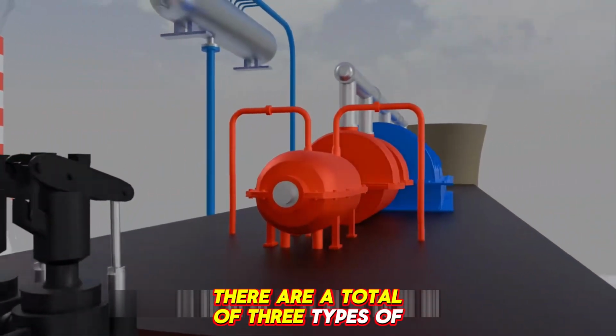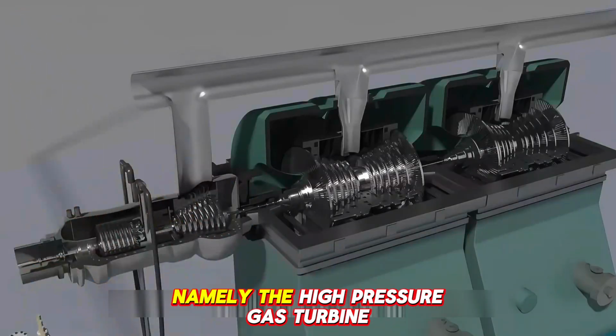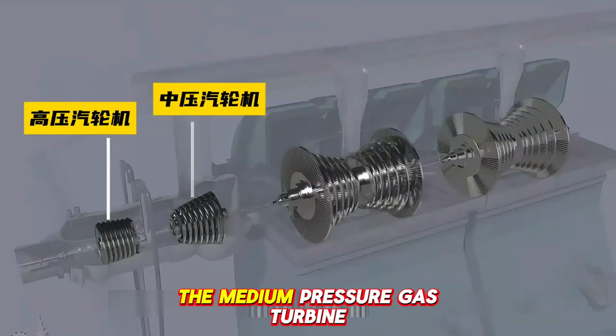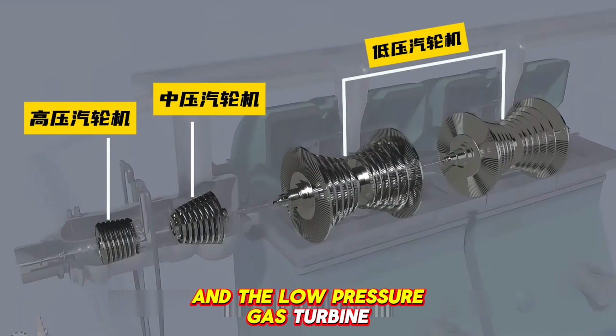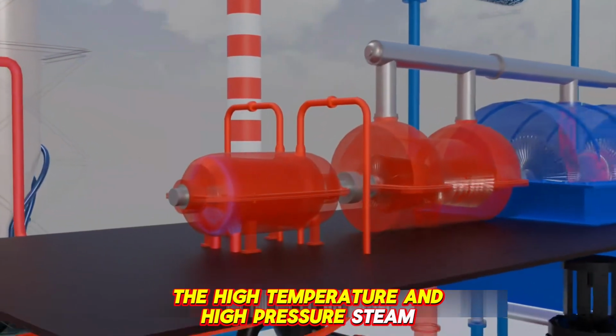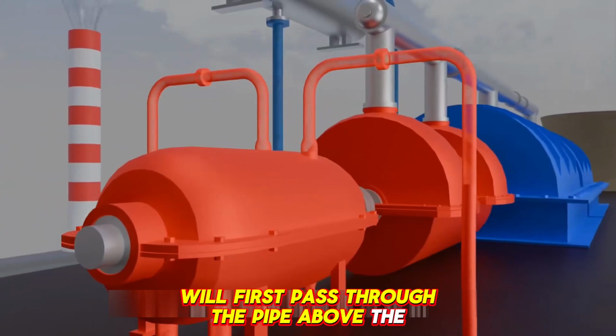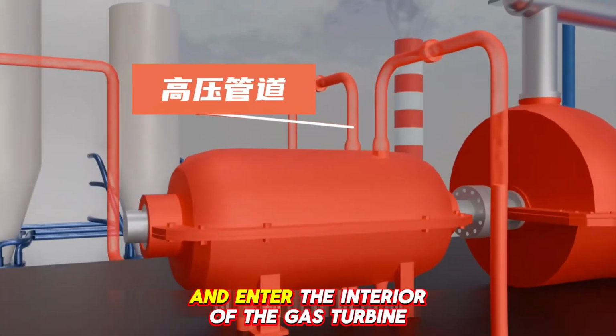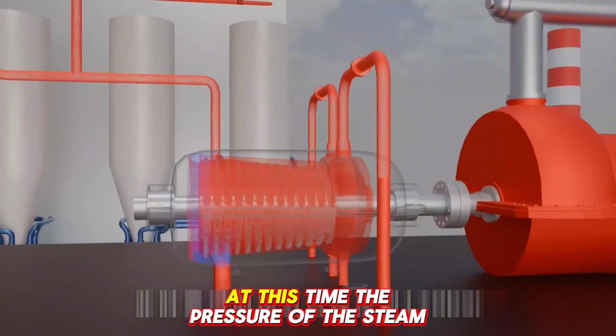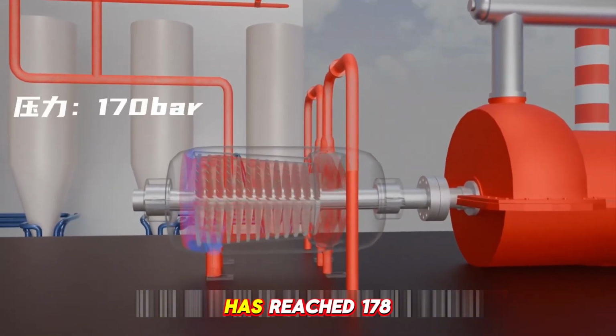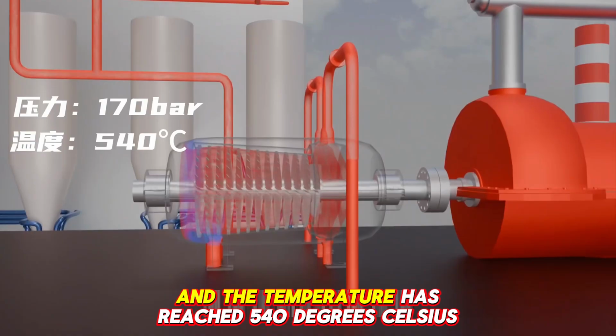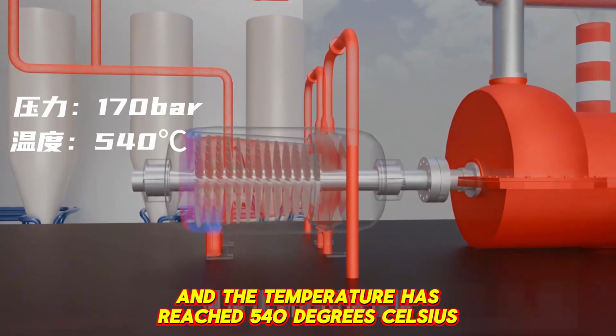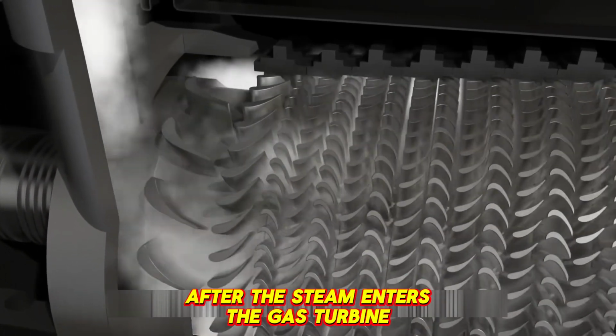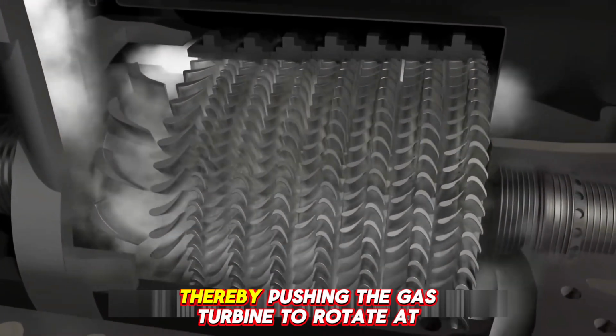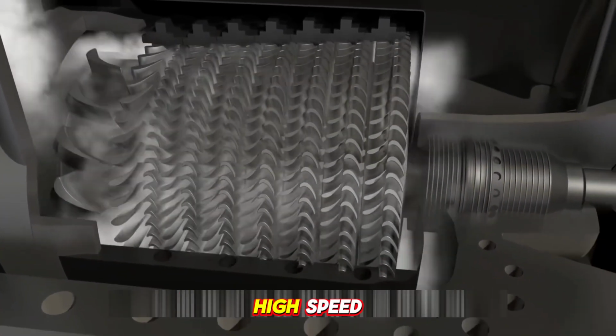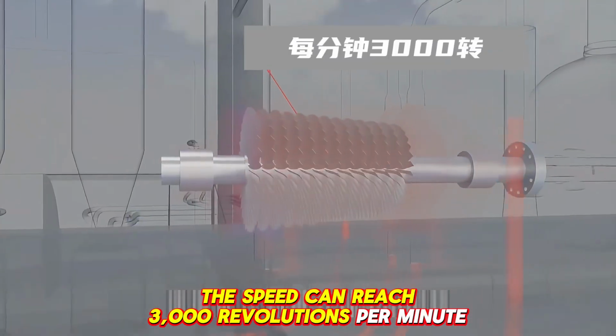There are a total of 3 types of gas turbine units, namely the high-pressure gas turbine, the medium-pressure gas turbine, and the low-pressure gas turbine. The high-temperature and high-pressure steam will first pass through the pipe above the high-pressure gas turbine and enter the interior of the gas turbine. At this time, the pressure of the steam has reached 178, and the temperature has reached 540 degrees Celsius. After the steam enters the gas turbine, it will expand rapidly, thereby pushing the gas turbine to rotate at high speed. The speed can reach 3,000 revolutions per minute.